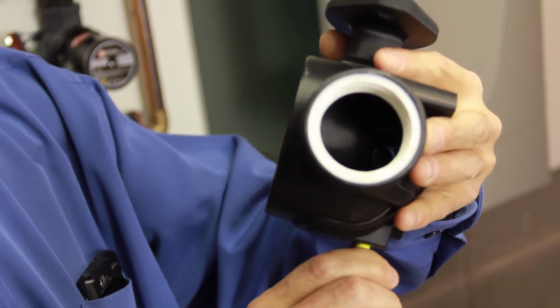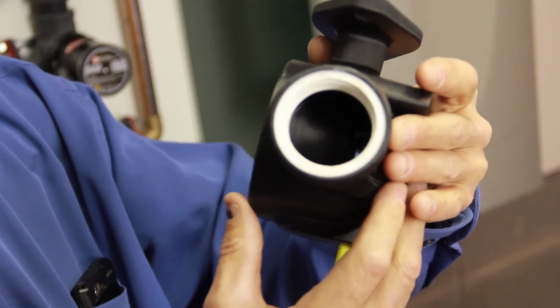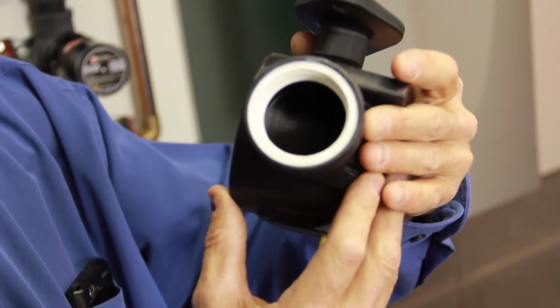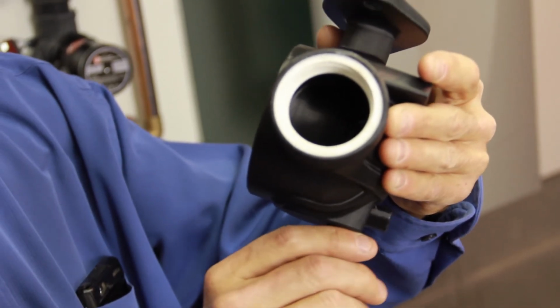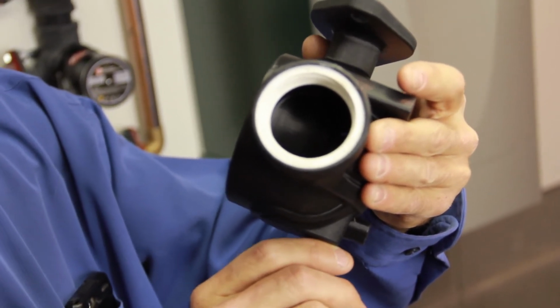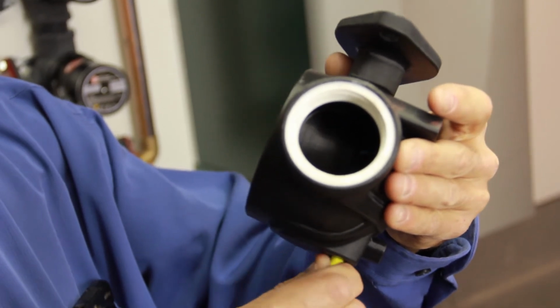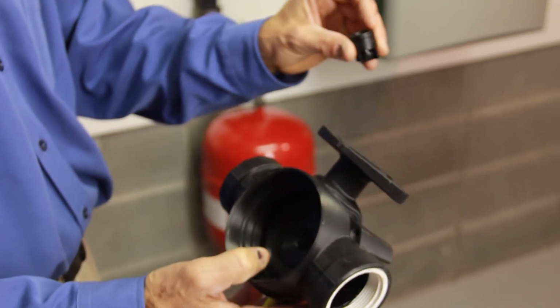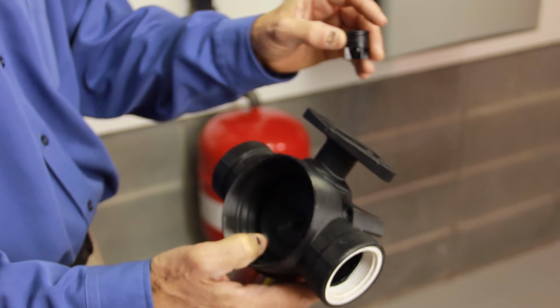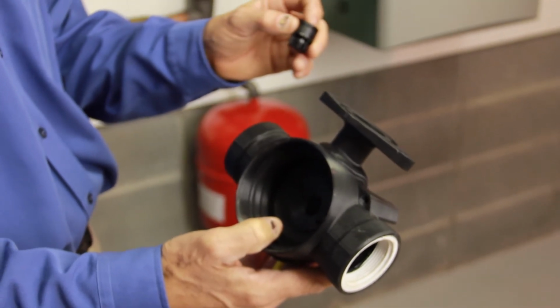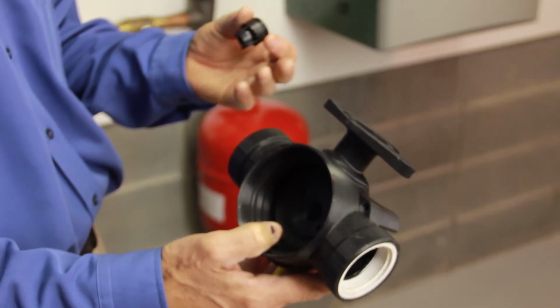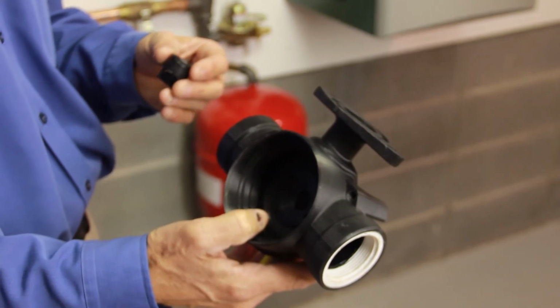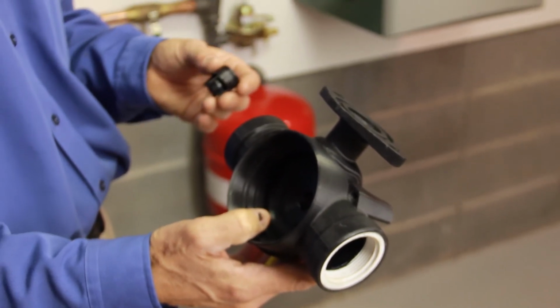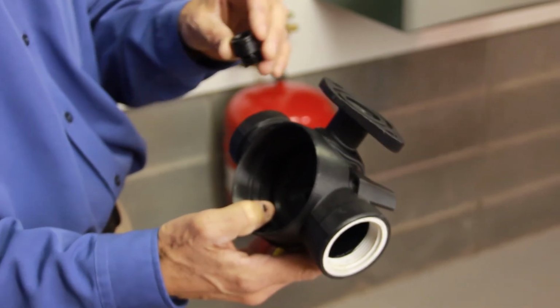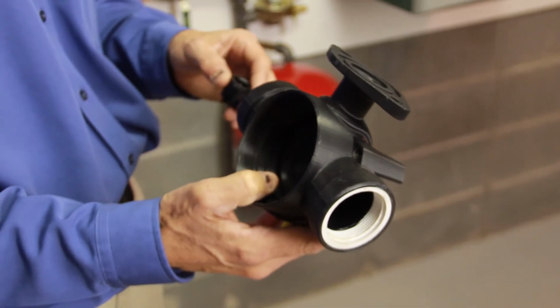The spacious internal volume of the volute gives us a very low pressure drop, which enables us to create this primary and secondary circuitry efficiently. There's a removable discharge check valve that we can install into the discharge nozzle of the pump if you want it. It's not always needed, but in certain cases it is. So we have the option of installing it or not using it.